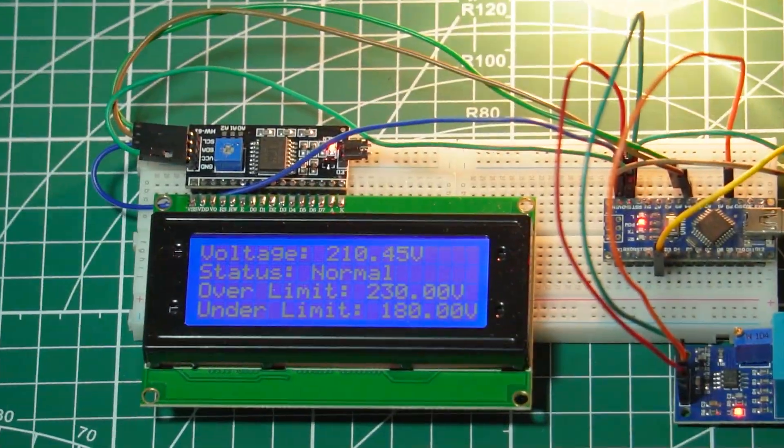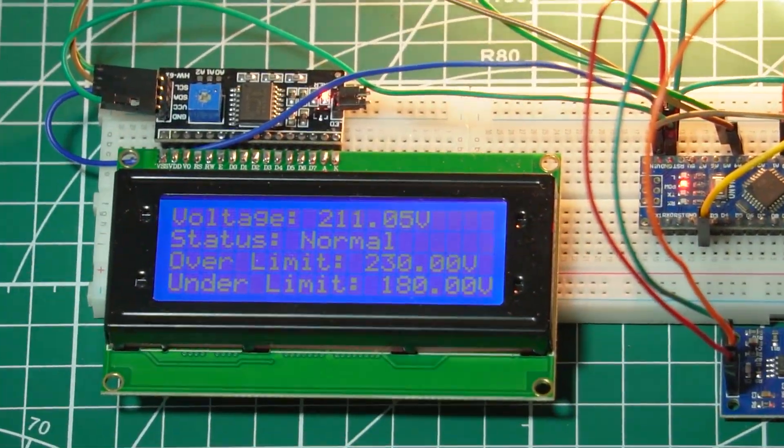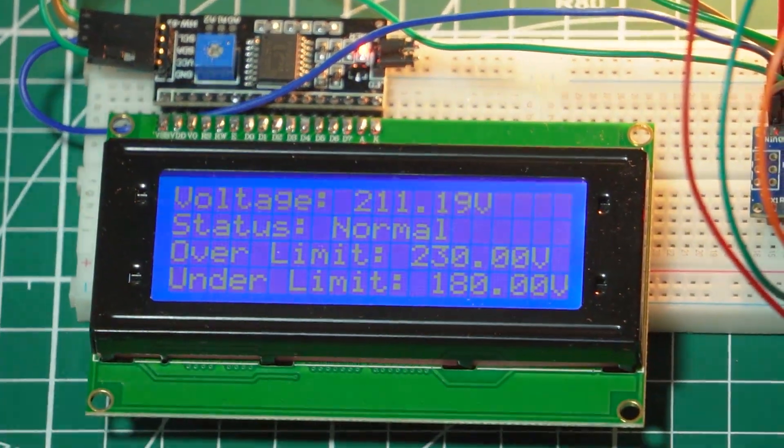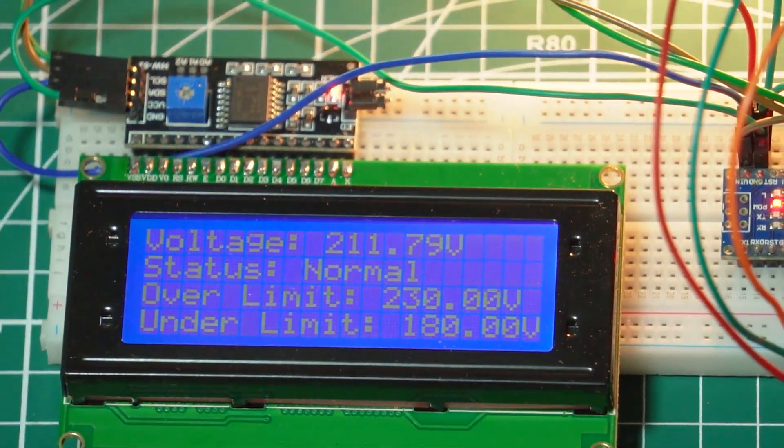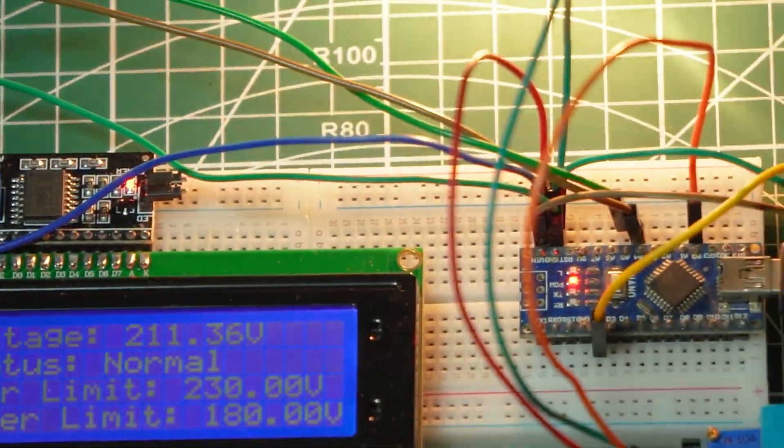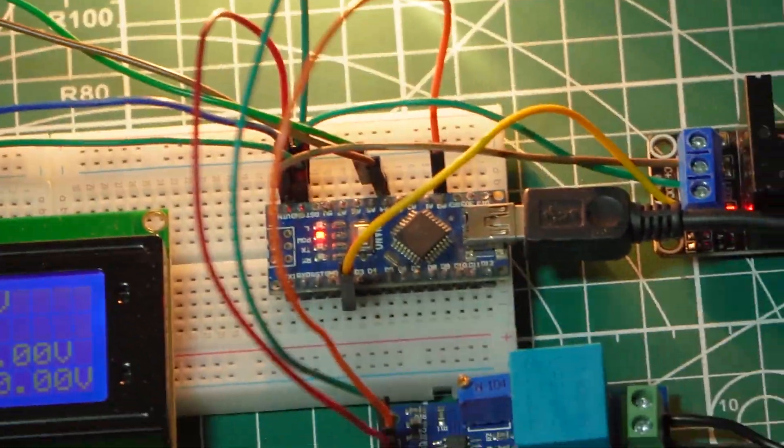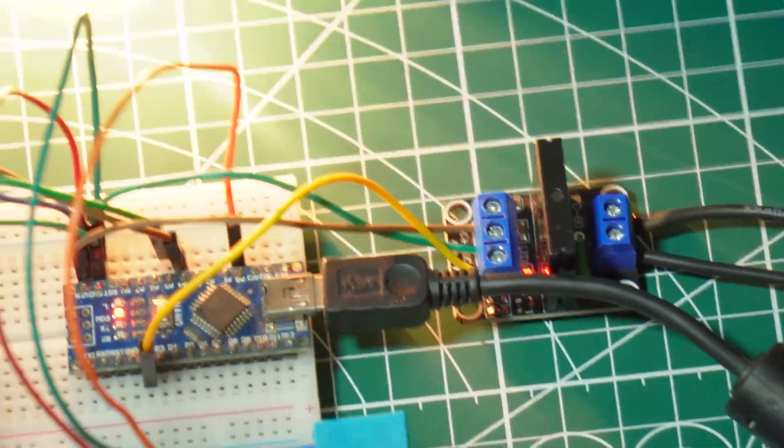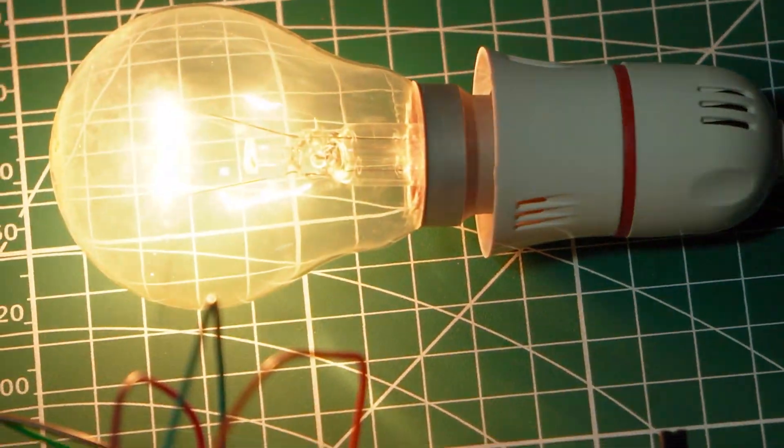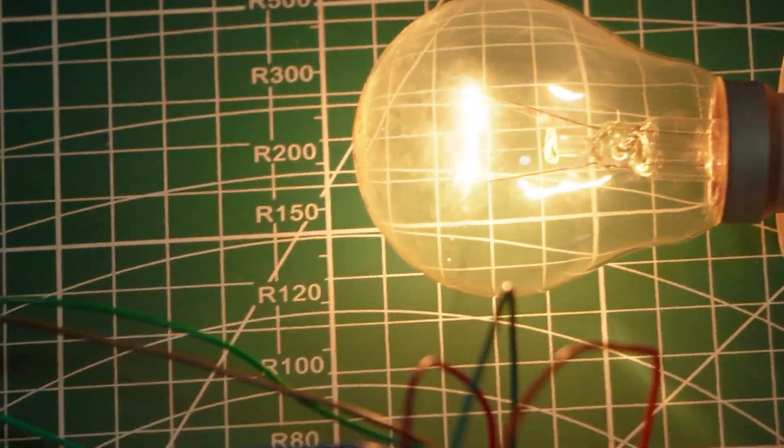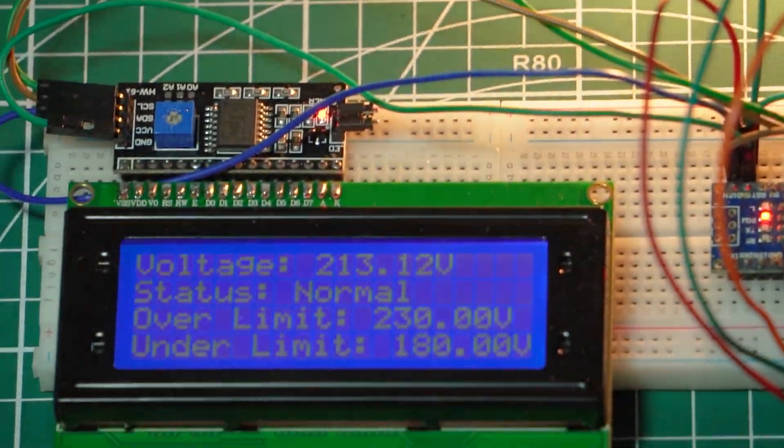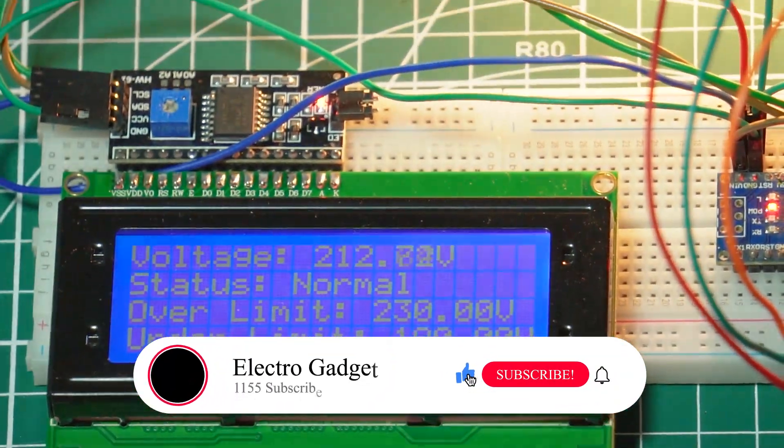With everything connected, let's power up the system and see it in action. Watch the LCD display as it shows the real-time voltage. We've set the thresholds at specific voltage limits, 230V for overvoltage and 180V for undervoltage.